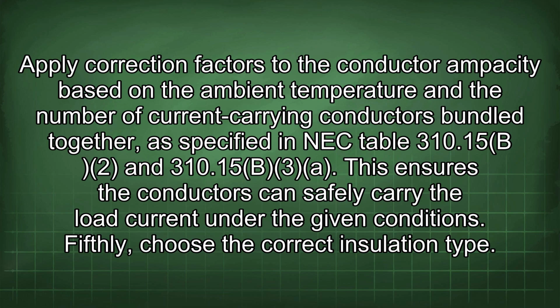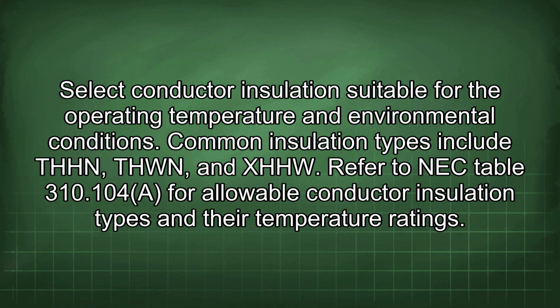Fifthly, choose the correct insulation type. Select conductor insulation suitable for the operating temperature and environmental conditions. Common insulation types include THHN, THWN, and XHHW. Refer to NEC Table 310.104 for allowable conductor insulation types and their temperature ratings.